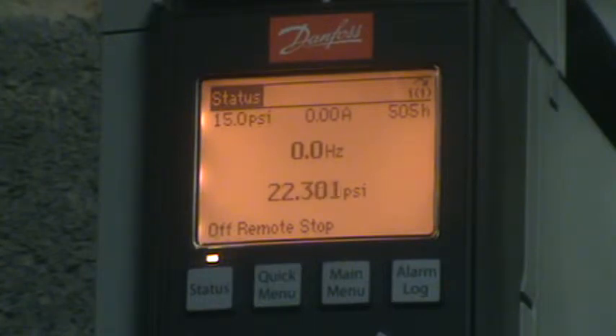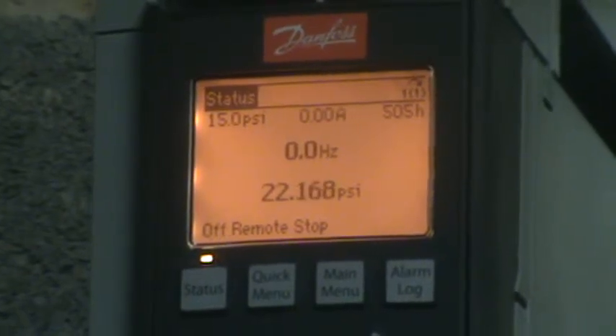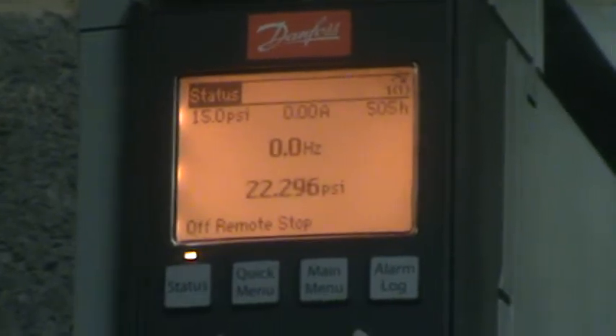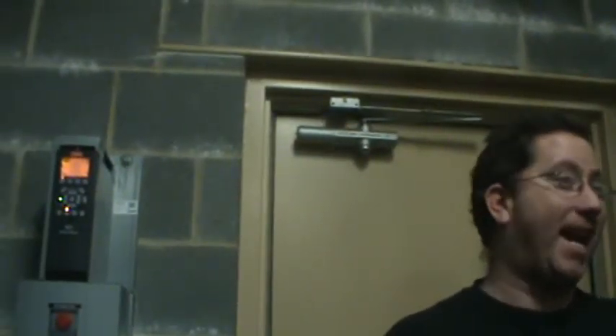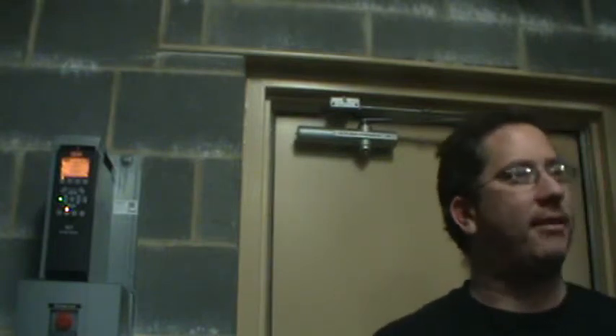Hit the info button. What's main menu and quick menu? Main menu and quick menu are things that normally I tell guys not to mess with. For the application you guys have here, you're barely scratching the surface of the ability and the logic in the drive. If you go into the main menu and start pushing buttons, you can change a parameter that may change 2 or 3 in the background.